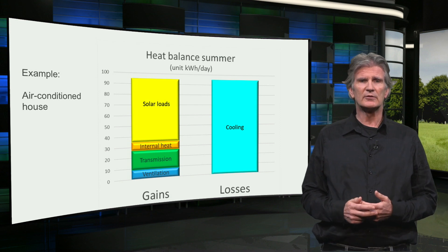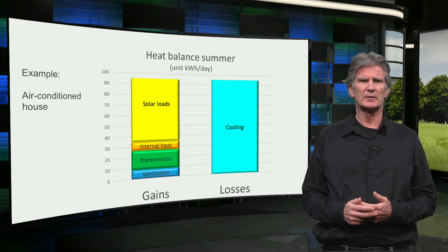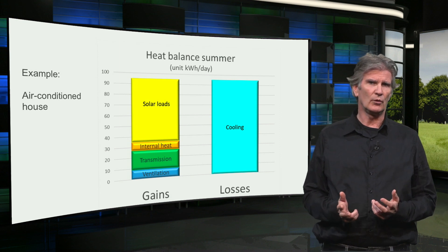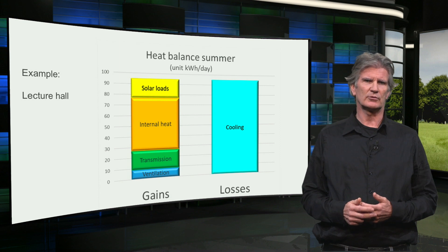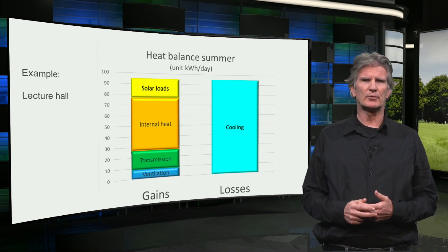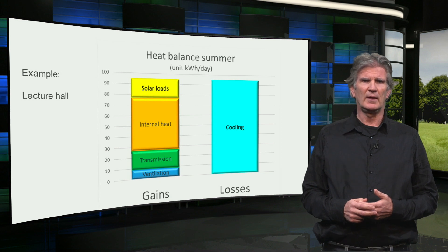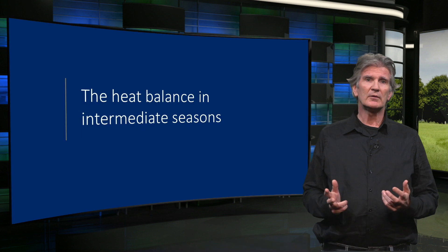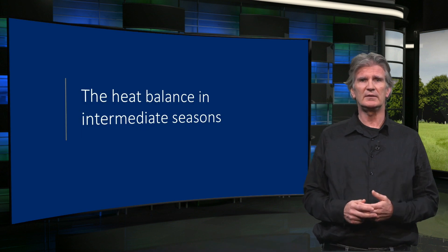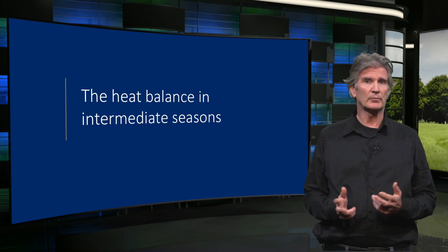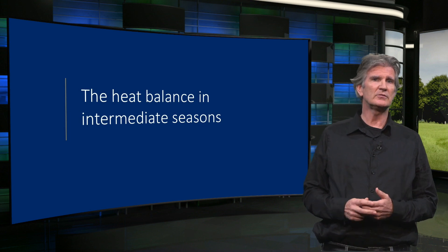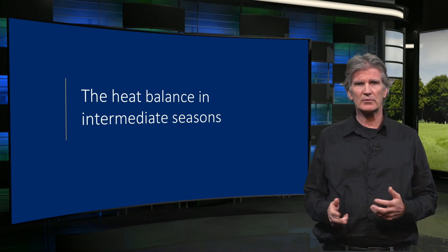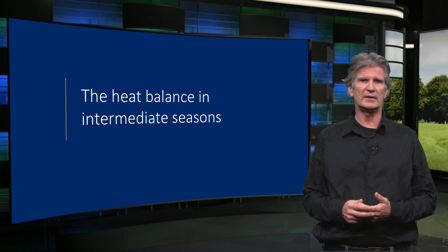This is an example for the heat balance on a hot summer's day in an air-conditioned building. In this case the internal heat loads are quite low and the solar gains are predominant. But for instance in a lecture hall, the internal heat load by people is the largest heat source. From the point of view of zero energy design, the intermediate seasons — spring and autumn — are even more interesting, because in these seasons you can achieve a comfortable climate without any energy demand for heating and cooling.